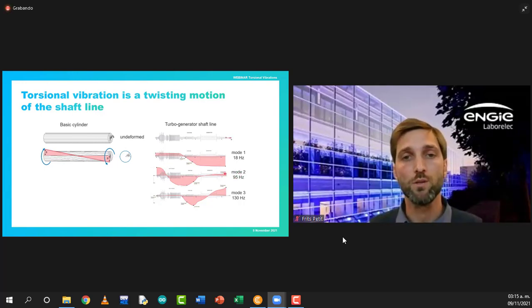You have higher modes as well, as you can see here for a gas turbine. For this example, 95 Hertz and 130 Hertz. For those modes, the deformation is more localized, for instance, to the gas turbine or to the generator. Typically, these higher modes are less excited by the grid, and so the most important modes are typically what they refer to as the subsynchronous modes, so modes below the grid frequency, below 50 or 60 Hz.